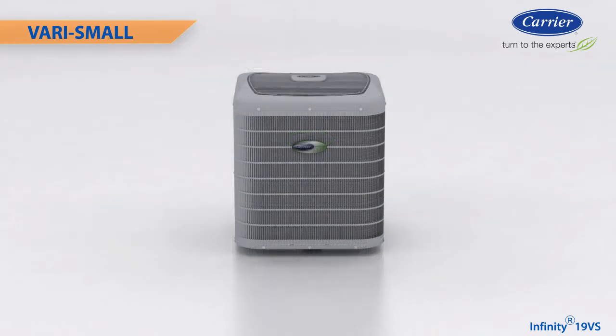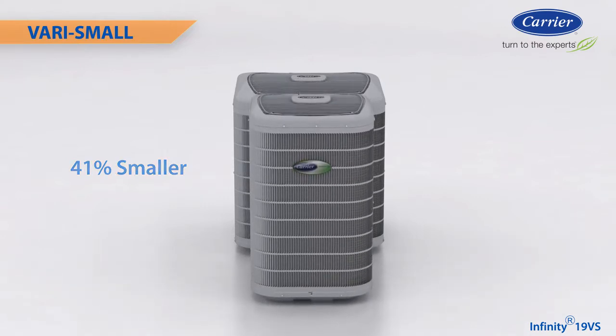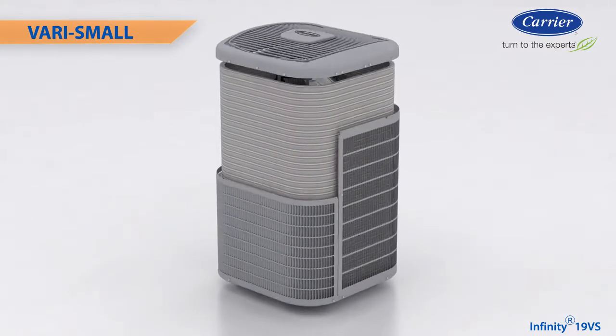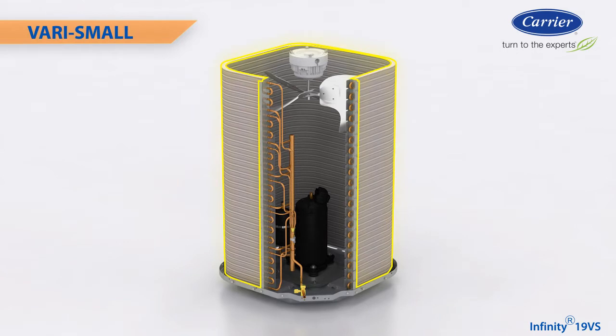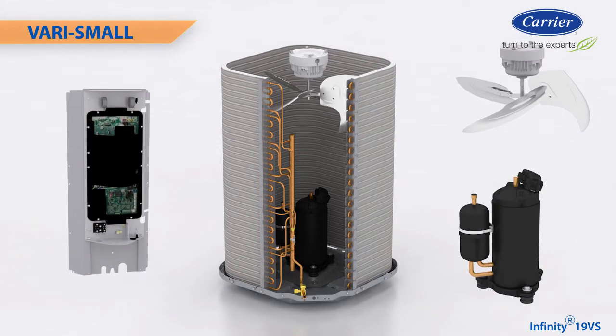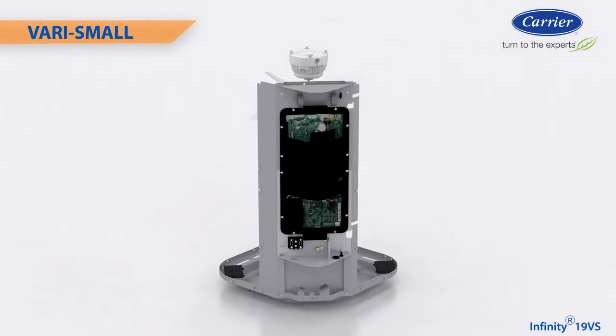For example, the three-ton model is 41% smaller in overall size than our current 17 SEER two-stage unit, and 76 pounds lighter as well, making it easier for dealers to handle, install, and stock. The keys to this size and weight reduction include our microtube coil technology and the efficiency advantages of the rotary compressor and new fan motor combined with a new inverter control. The new fan motor is more compact than other ECM motors because its control is built into the inverter instead of attached to the motor. Similar compressor and fan motor technology is being used in millions of units around the world with proven reliability.